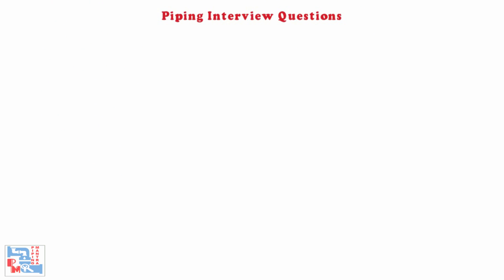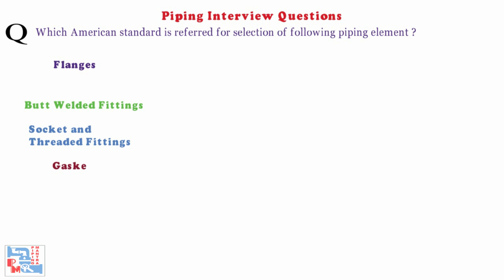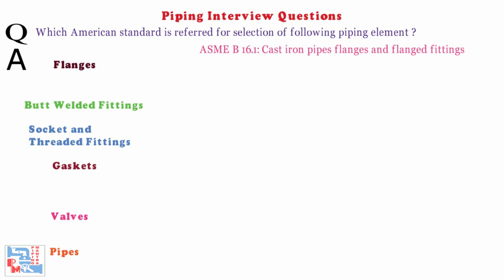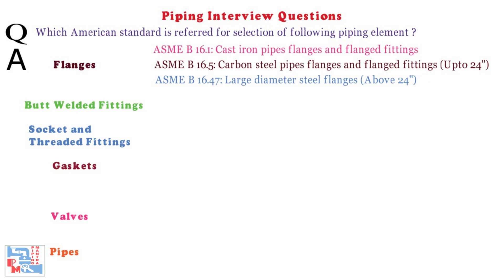Next: which American standards are referred to for selection of piping elements — flanges, butt welded fittings, socket and threaded fittings, gaskets, valves, and pipes? For flanges: ASME B16.1 is for cast iron pipe flanged fittings. ASME B16.5 is for carbon steel pipe flanges and flanged fittings up to 24 inch. ASME B16.47 is for large diameter steel flanges above 24 inch.